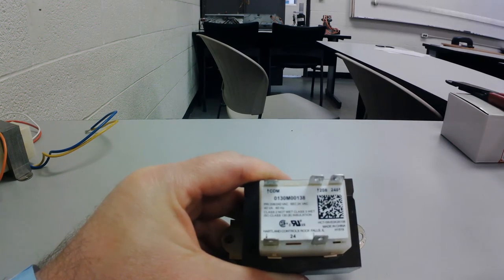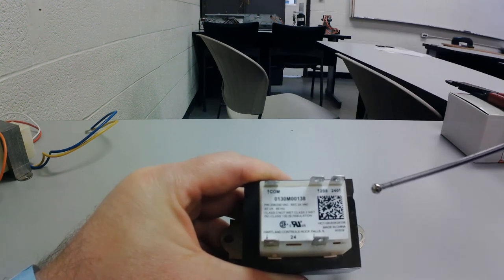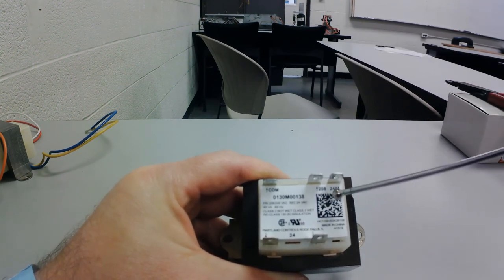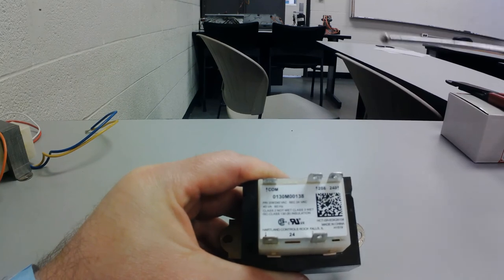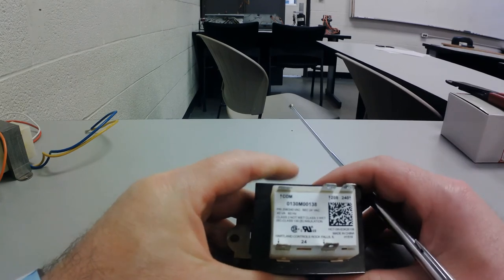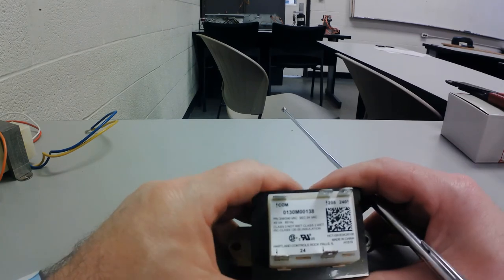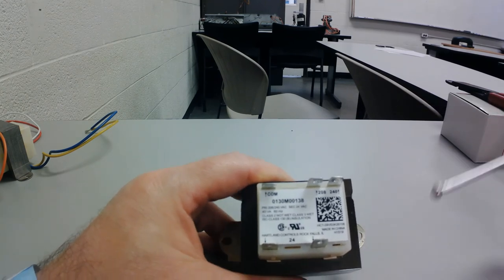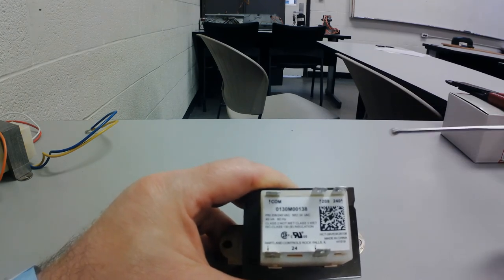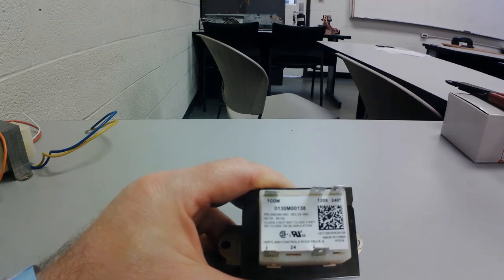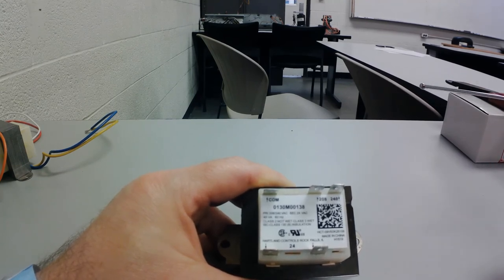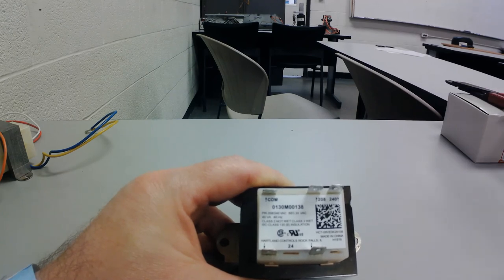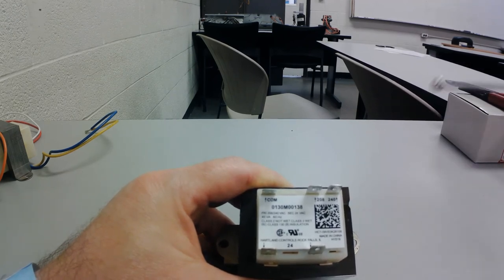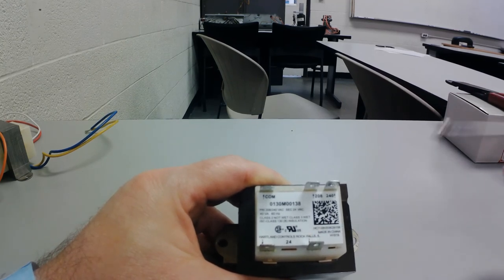So make sure when you go out there, especially to these rooftop package units, it was always a big deal for me because I didn't like seeing the 22 volts or the 23 volts. You'll get low enough voltage sometimes, depending on how close you are to the substation, the power station, whatever you want to call it. You could get a little bit of chatter off of your contactors and relays because the voltage is just high enough to engage the coil and cause the switches to move. But once it starts to pull that small amount of amp draw, it may cause the switches to chatter. The coil will energize and de-energize because you're kind of over-amping your secondary side, okay?